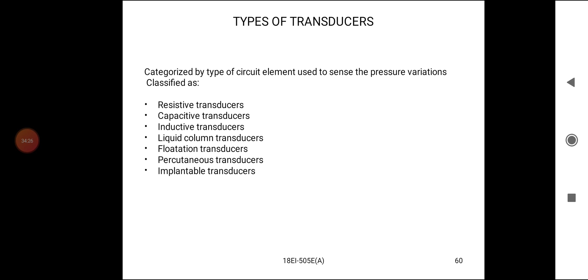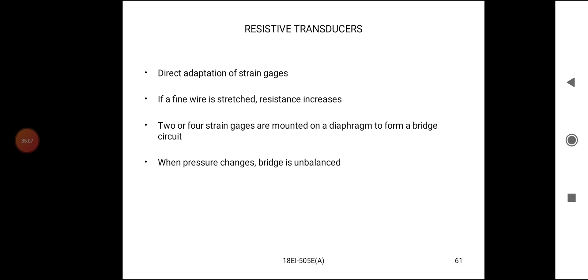Resistive transducers: direct adaptation of strain gauges. If a fine wire is stretched, its resistance increases. The strain gauge is a resistive element. Two or four strain gauges are mounted on the diaphragm to form a bridge circuit. Here we can use a 4-arm bridge circuit. When pressure changes, the bridge is unbalanced.